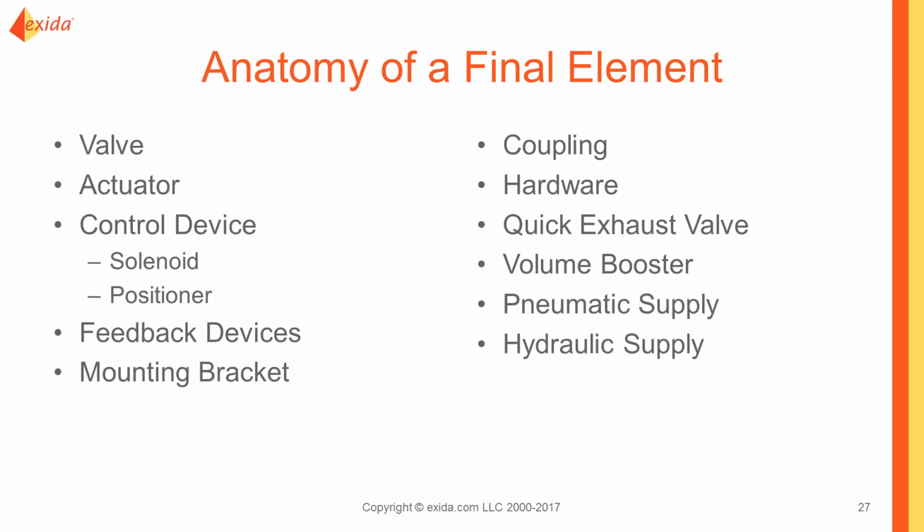So those are components that need to be included not only from a verification perspective, but also from a design evaluation. Are they designed well such that they're going to perform their function? And we want to consider if we have a dual or potentially a dual acting design where the availability of pneumatic supply and hydraulic supply also has to be considered.